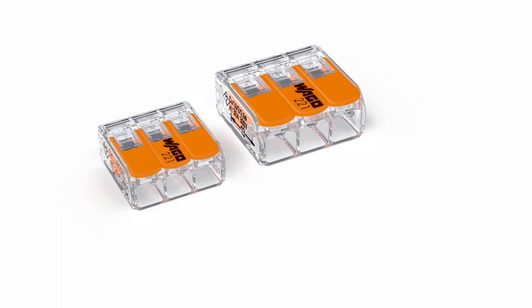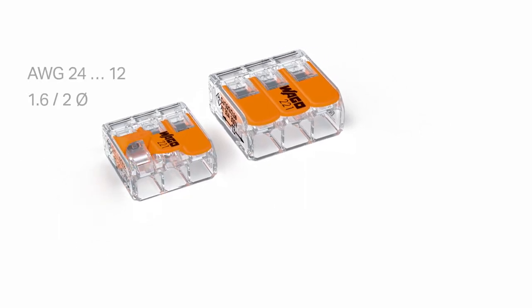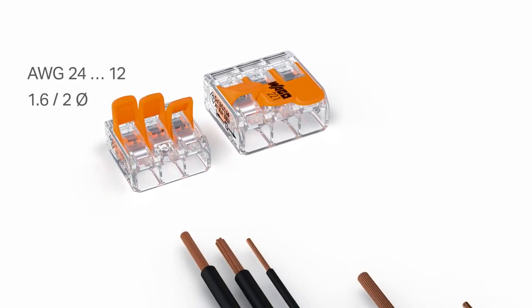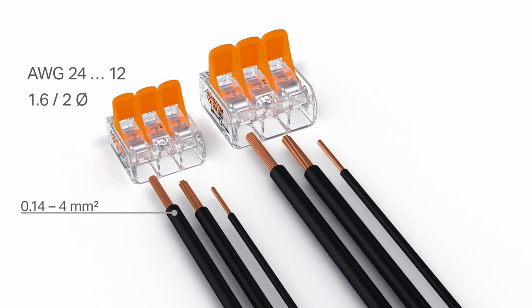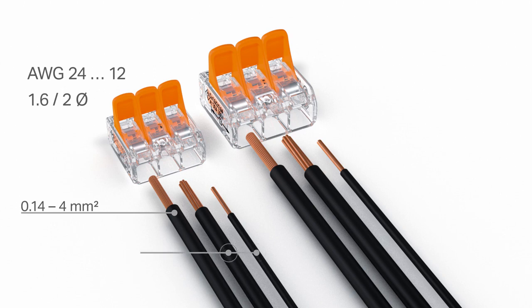The 4 square millimetre 32 amp version accommodates fine stranded conductors from 0.14 to 4 square millimetres as well as solid and stranded conductors from 0.2 to 4 square millimetres.